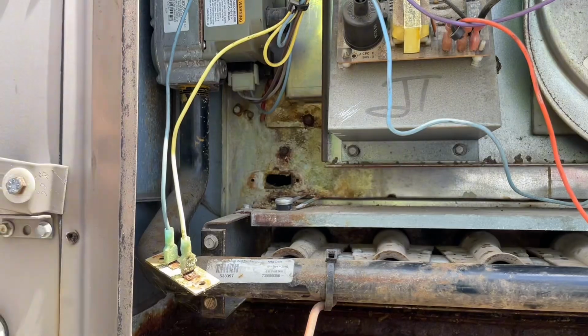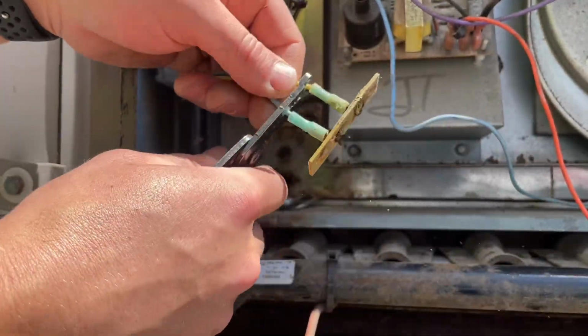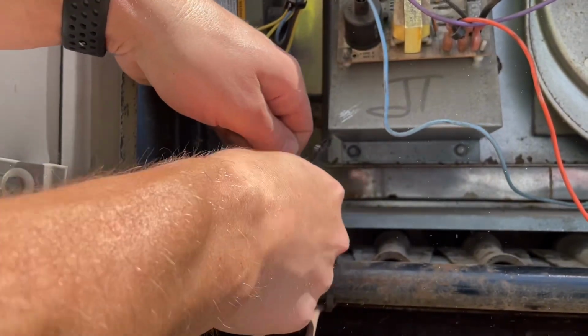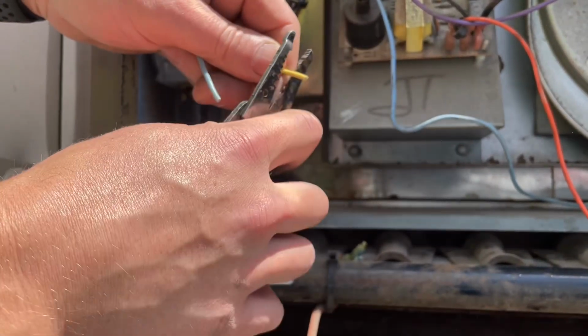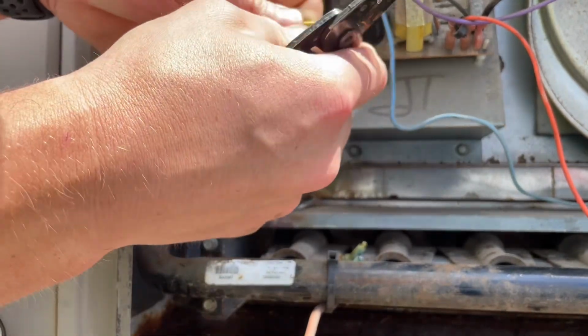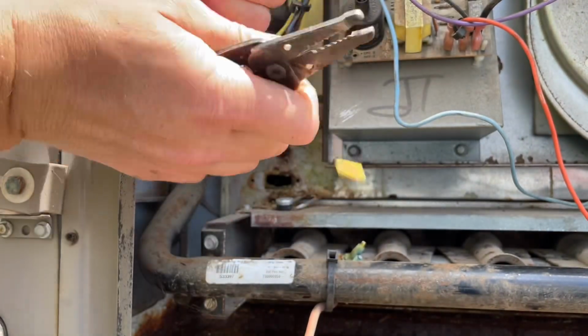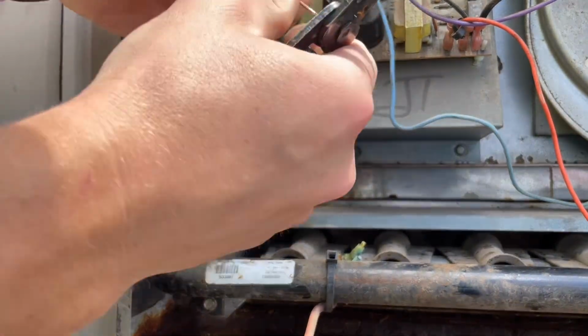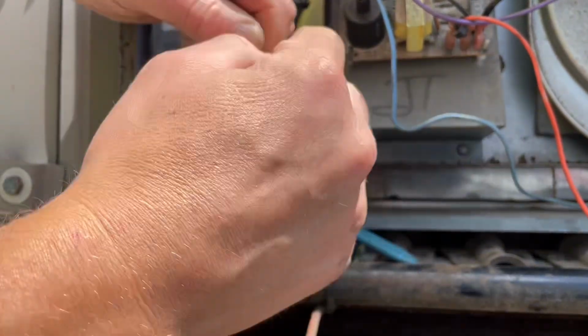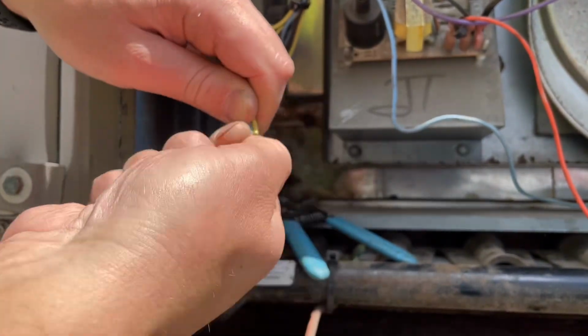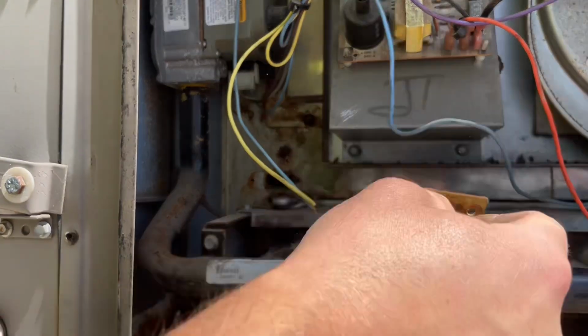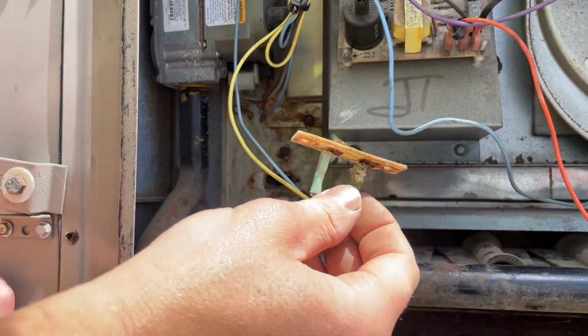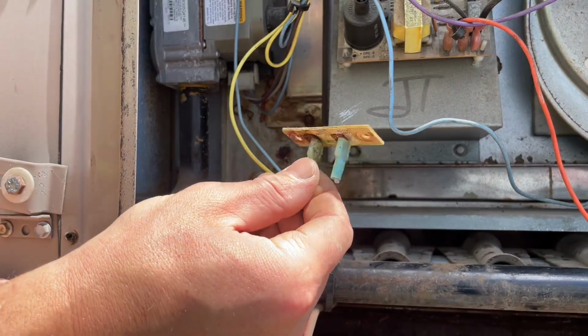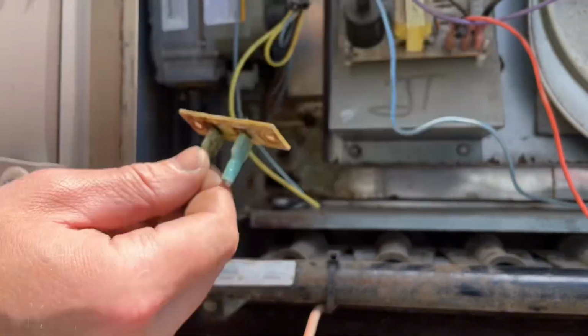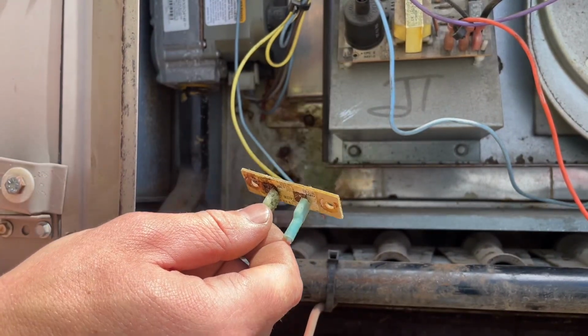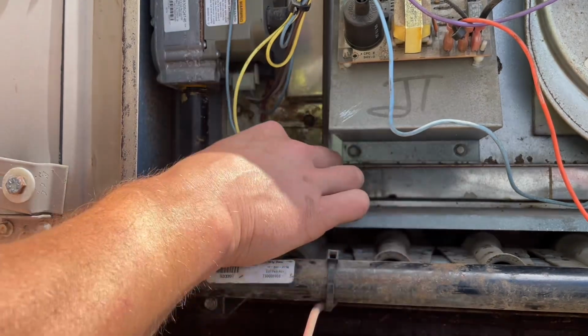And finally, before we go pick up this limit switch, let's cut that off. We're going to jump out this limit switch and make sure our inducer motor stays off. You never know, right? Could have a faulty board, a faulty relay as well, keeping that inducer motor on 24/7. By the way, guys, that's a safety in this unit. A safety procedure that they will all take is if this limit switch ever did fail, that inducer motor will run 24/7 to get rid of any heat that could be built up inside of the machine.